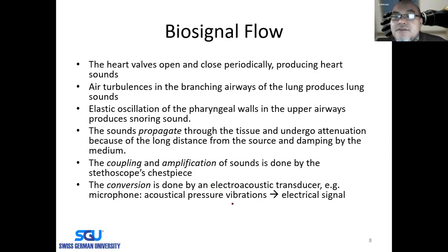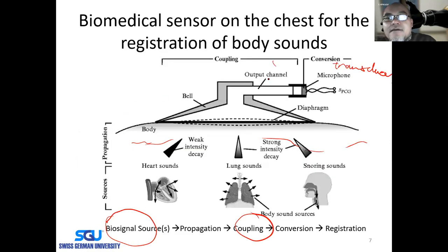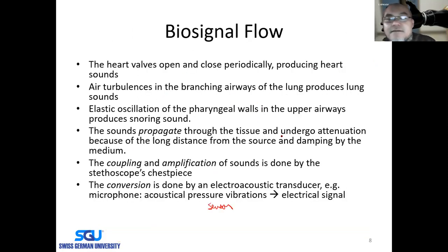Usually this is what we call the sensor. But in this particular case of biomedical equipment, the sensor is the whole chest piece. The whole thing could be set as a sensor, while the microphone at the end of this line could be called the transducer. Transducer is more specific.